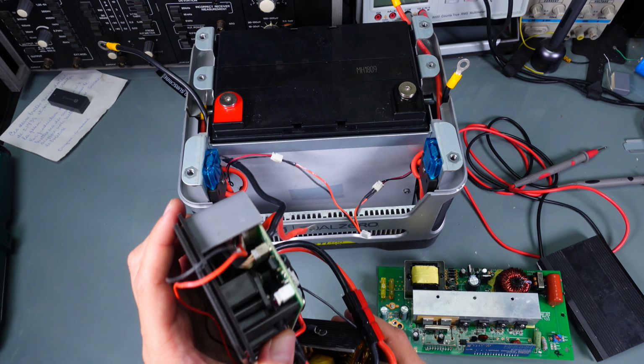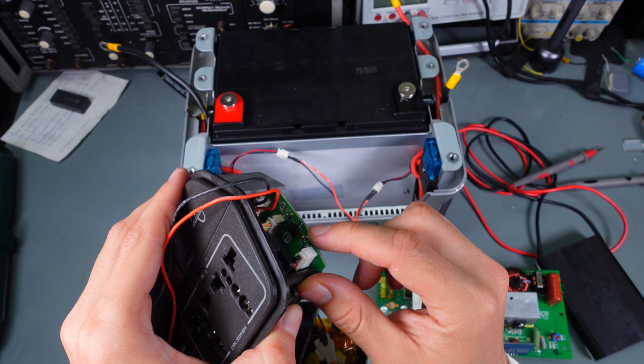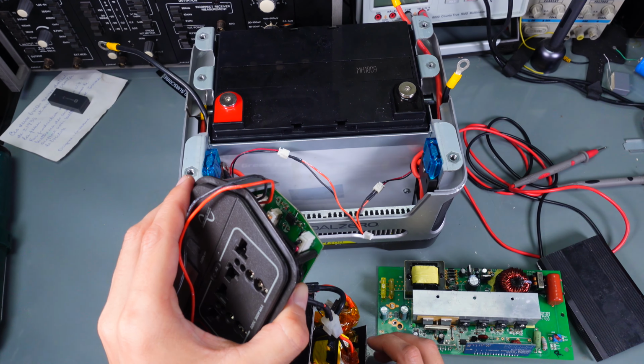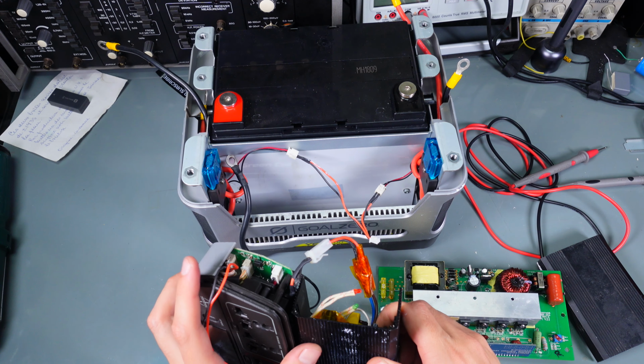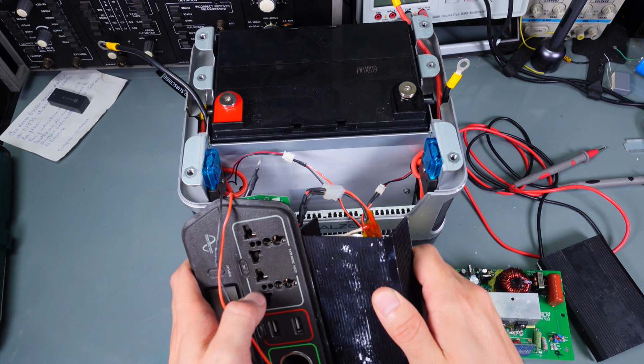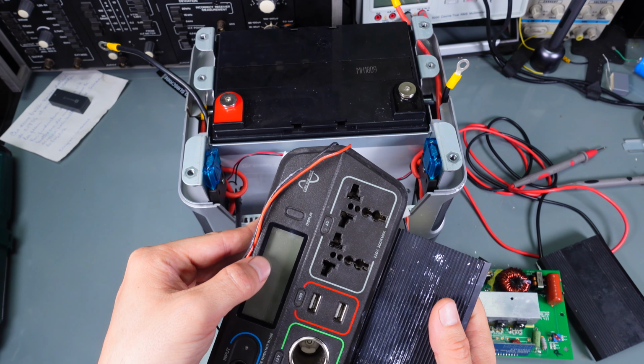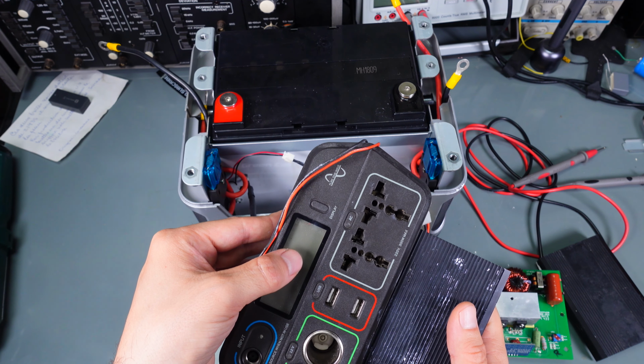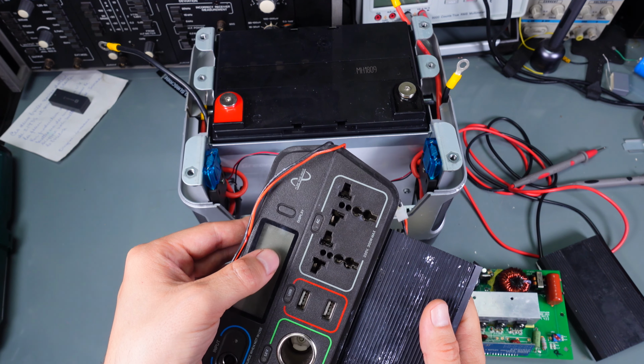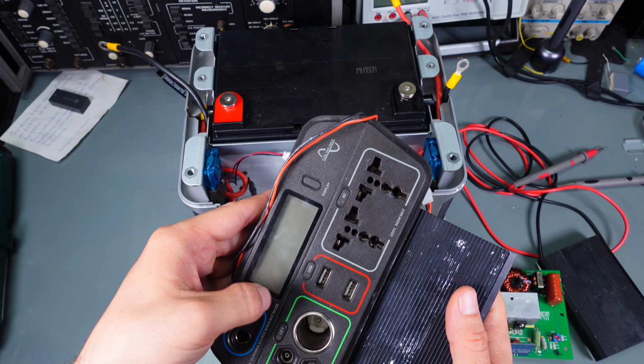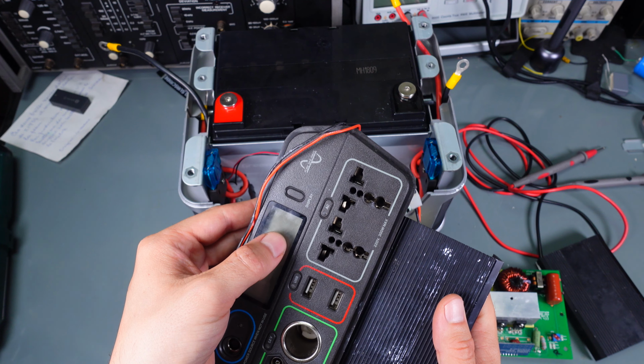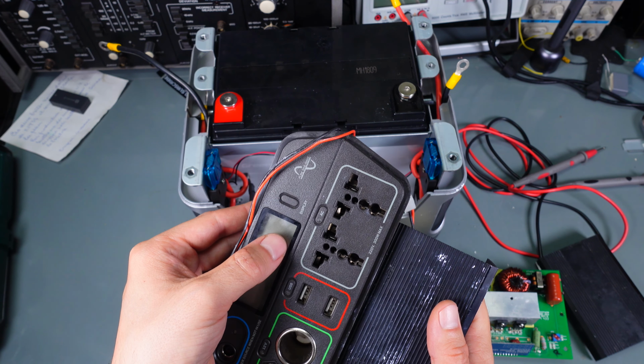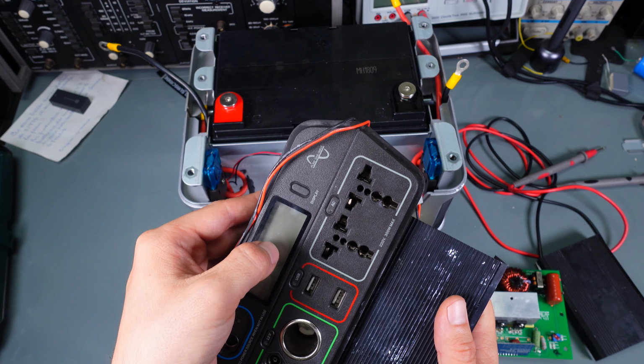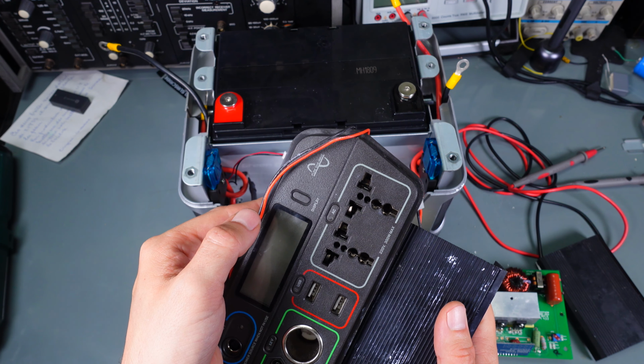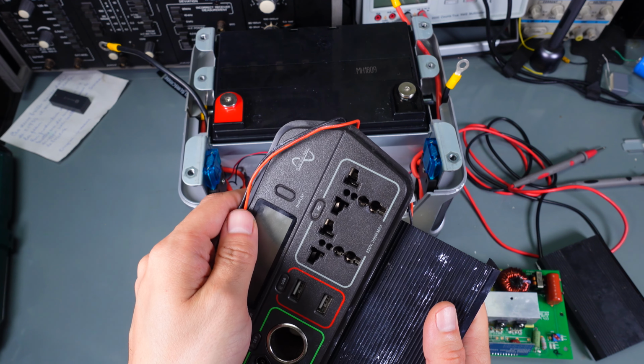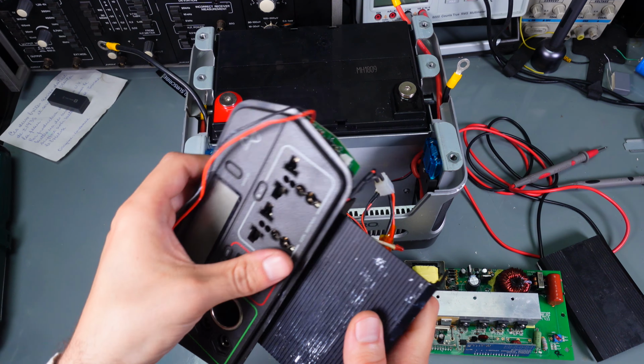That section has an opto isolator here, and it detects whether the inverter is working and creating the correct voltage. You can see that by a small exclamation mark during startup of the inverter - it knows it's turned on but doesn't yet have the correct voltage, so it shows the problem, but after a couple seconds it goes away and indicates everything is working nicely.